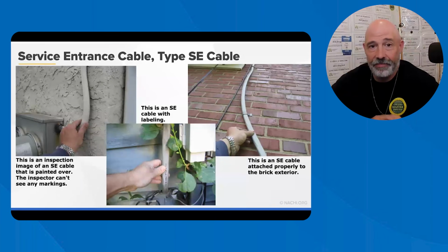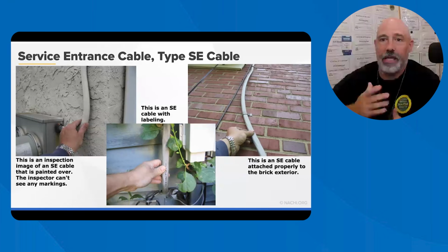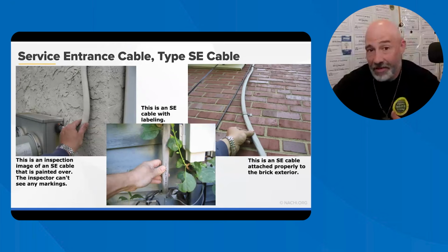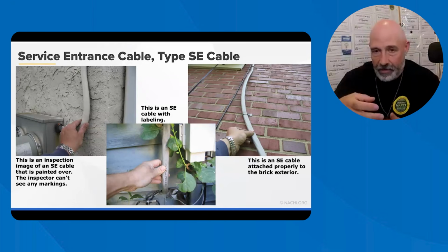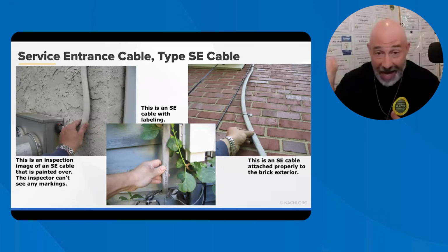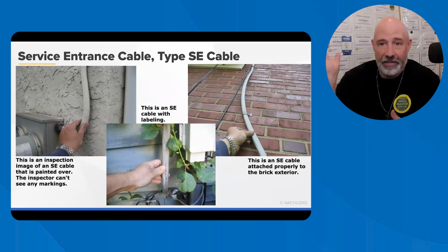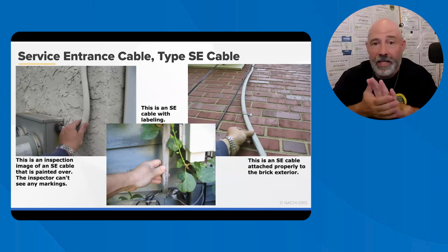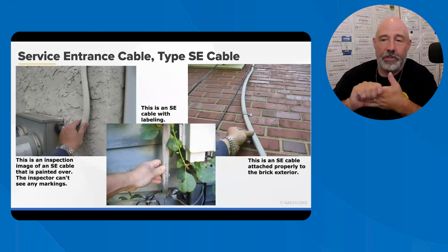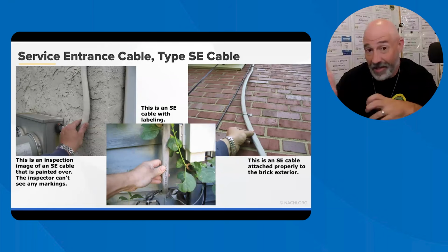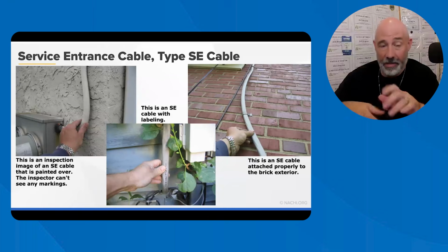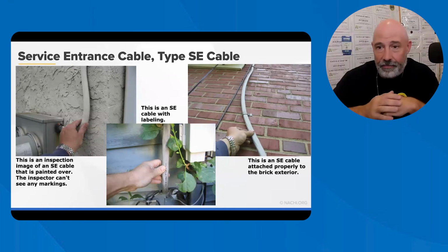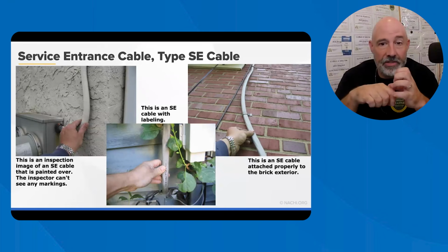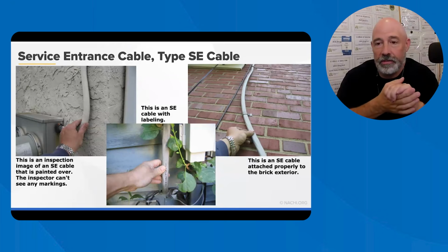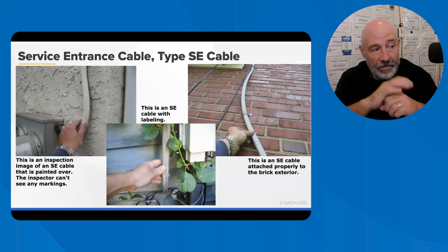The SE, which is service entrance, you hear that quite a bit. The cable assembly is designed with a high degree of resistance to mechanical damage and the sun's ultraviolet light. So, for instance, especially here in Florida, that sun is hot, and for that reason it is not installed in a conduit, but it's attached directly to the building, so it doesn't overheat. If it's located someplace where it's likely to be physically damaged, like by car doors, etc., it has to be in conduit, and it should still feature a gooseneck, of course, and a service head cap.